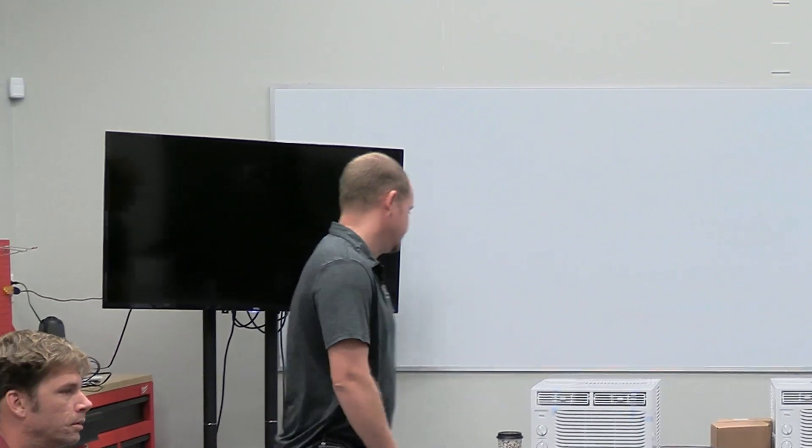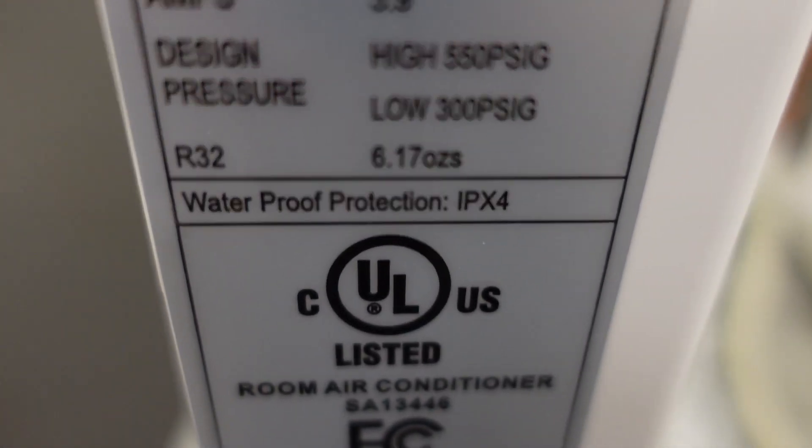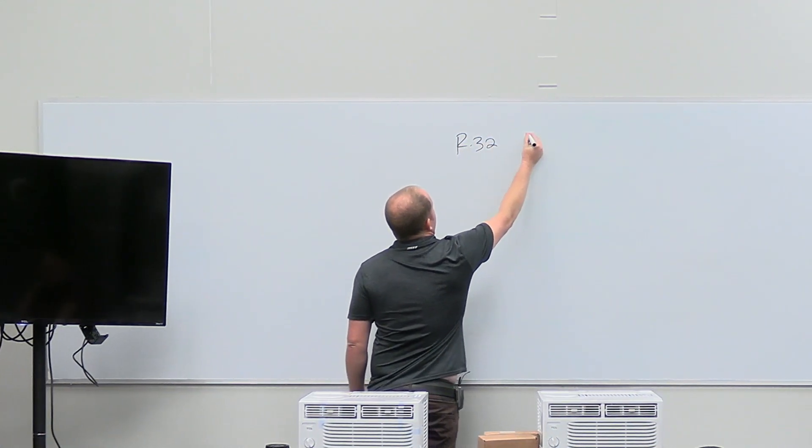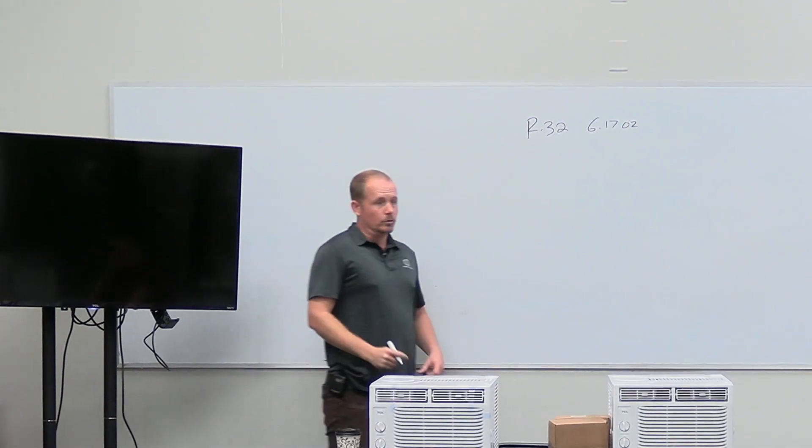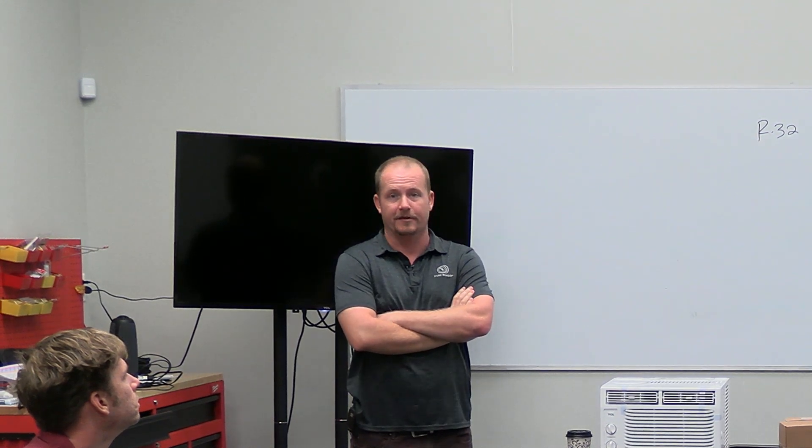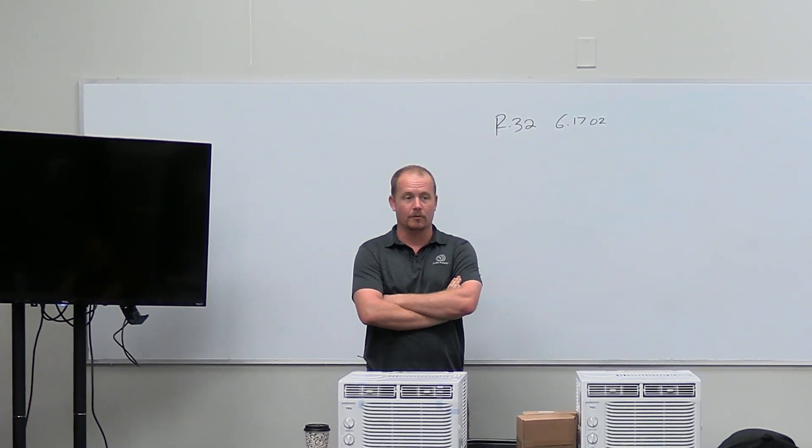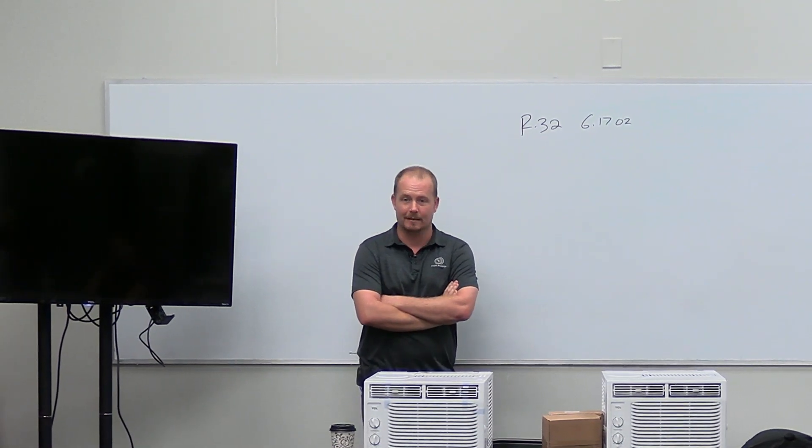These come with a factory charge in them. Anybody care to tell me what the factory charge is on the data plate there? R32, 6.17 ounces. There are rules in the U.S. about how much of this type of refrigerant can be in the equipment. This type of refrigerant is a flammable refrigerant. More specifically, it is what is called a mildly flammable refrigerant. It is an A2L.